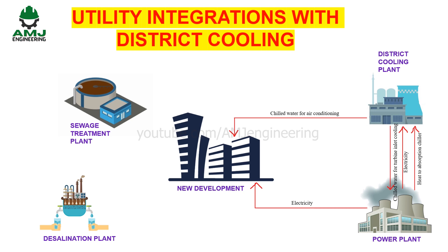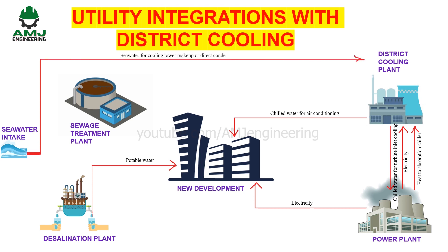The good thing here is that makeup water does not have to be drinking water quality. The following water sources can be used in cooling tower makeup. Seawater, when available, is a great option, but it requires much more expensive equipment that can withstand the aggressive nature of seawater quality, such as corrosion-resistant cooling tower materials like PVC or titanium heat exchangers in a direct condenser cooling system. Other low-quality waters can also be used, including TSE water.